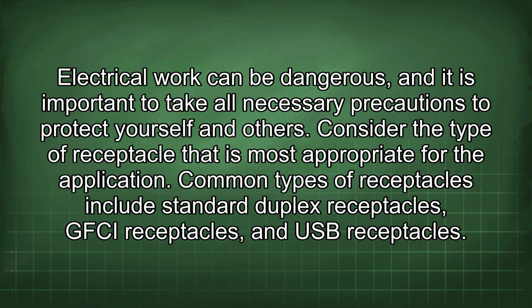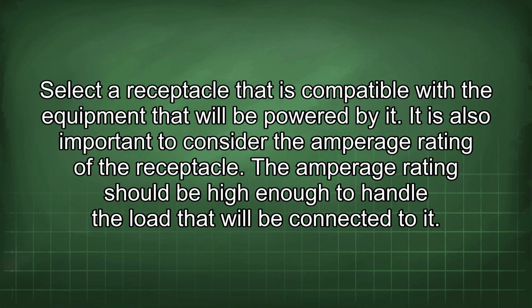Consider the type of receptacle that is most appropriate for the application. Common types of receptacles include standard duplex receptacles, GFCI receptacles, and USB receptacles. Select a receptacle that is compatible with the equipment that will be powered by it. It is also important to consider the amperage rating of the receptacle. The amperage rating should be high enough to handle the load that will be connected to it.